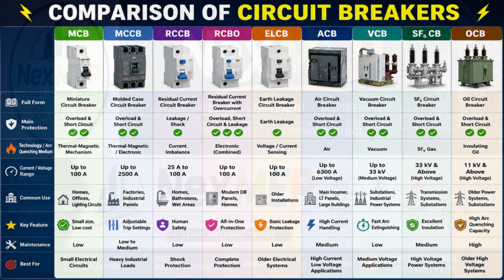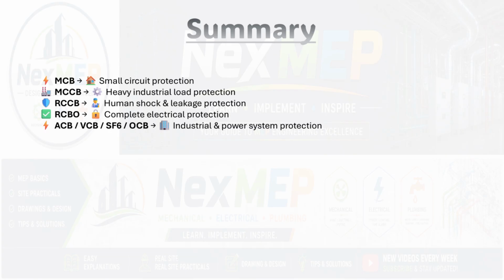Now the bigger ones, ACB handles up to 6300A for low-voltage main incomers. VCB goes up to 33 kV for medium-voltage substations. SF6 handles 33 kV and above for high-voltage transmission. And OCB, older high-voltage systems from 11 kV upward. The key takeaway? As the voltage and current go higher, you need more sophisticated arc quenching, from air to vacuum to SF6 to oil. So let's do a quick summary before we wrap up.